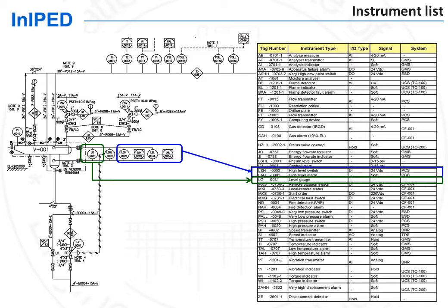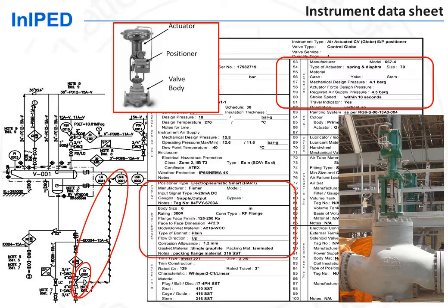The process data sheet of a control valve, for instance, shows the functional requirements, which is the operating range — the extreme operating cases — as well as the maximum differential pressure for sizing of the actuator and the fail-safe position. The instrumentation discipline complements this process information with mechanical, as well as electrical and instrumentation information.